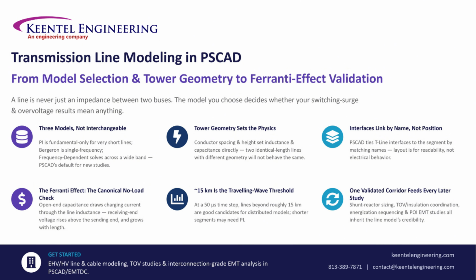PSCAD gives you 3 options, and they're not interchangeable. PI sections are fundamental frequency only, reserved for very short lines. Bergeron is a distributed traveling wave model, but still single frequency, which makes it ideal for load flow and power frequency checks. The frequency-dependent phase model solves across a wide frequency band and is PSCAD's own recommended default for any new study.